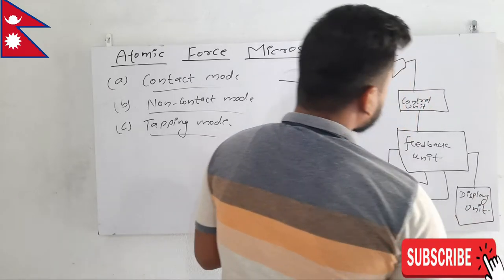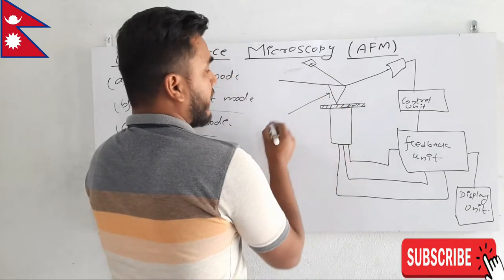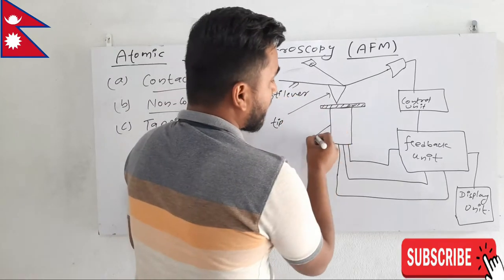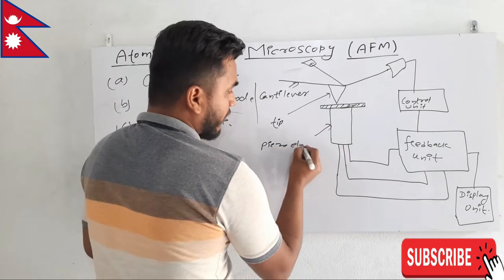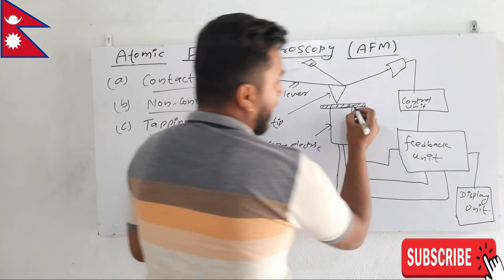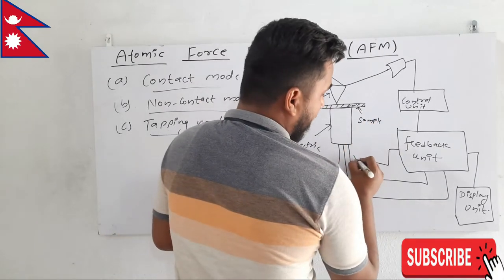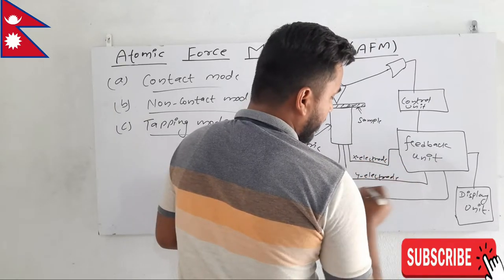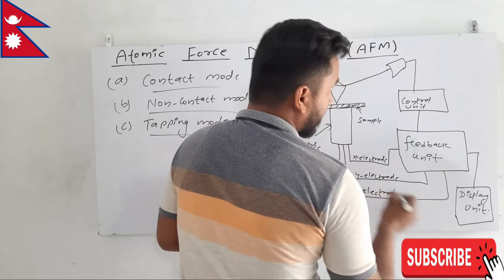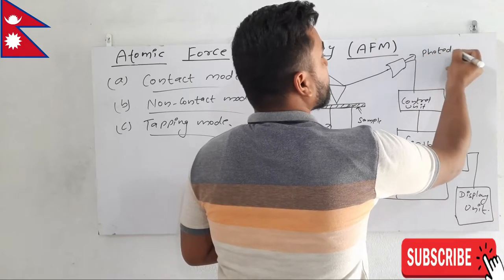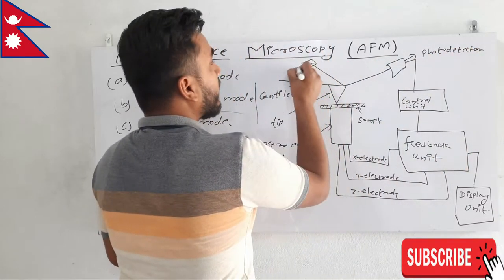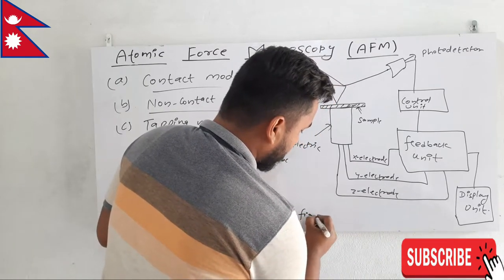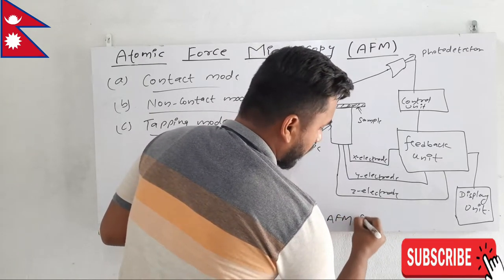Now, the names of the components: this is the tip, this is the cantilever, this is the piezoelectric cube, and here is the sample. These are the X electrode, Y electrode, and Z electrode. Here is the photo detector and here is the laser light. This is the complete figure of the atomic force microscopy setup.